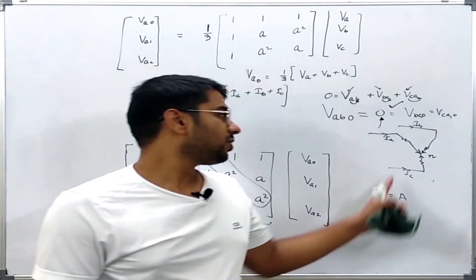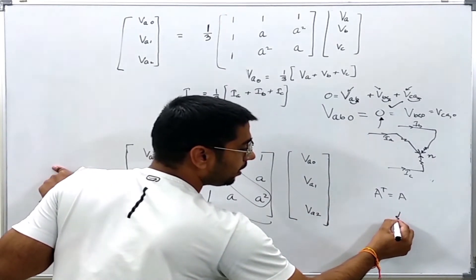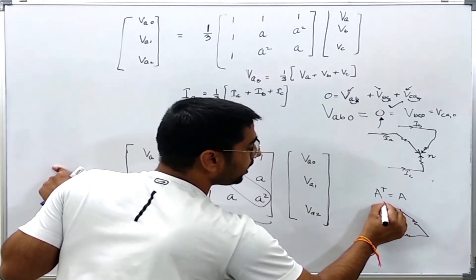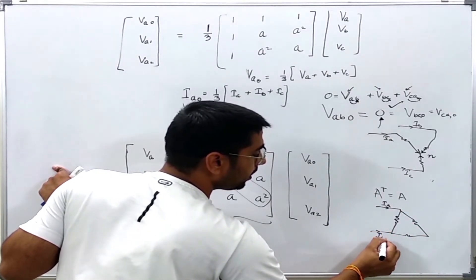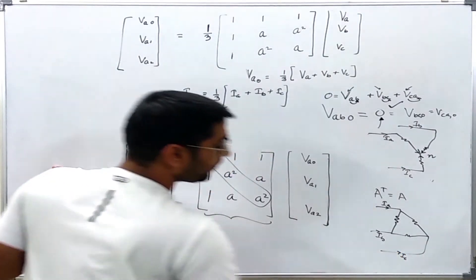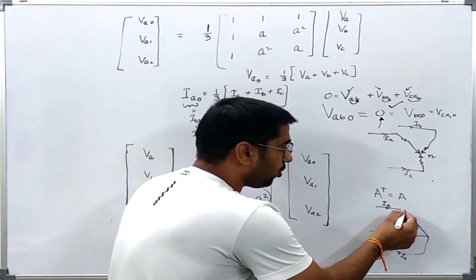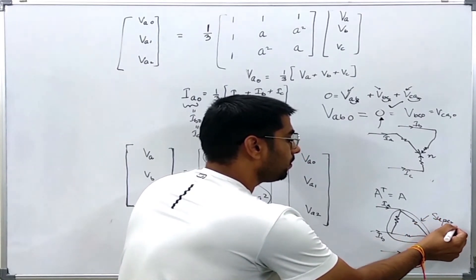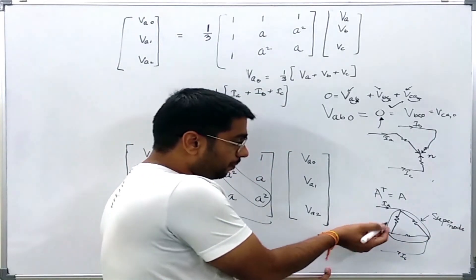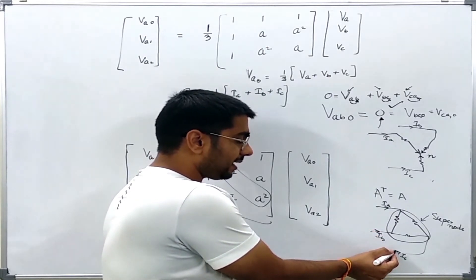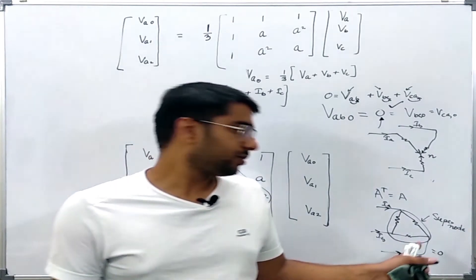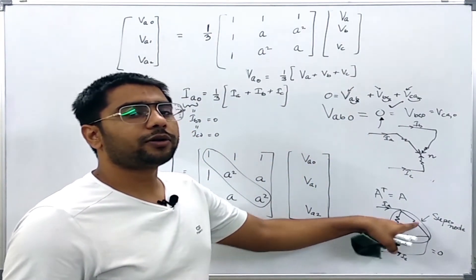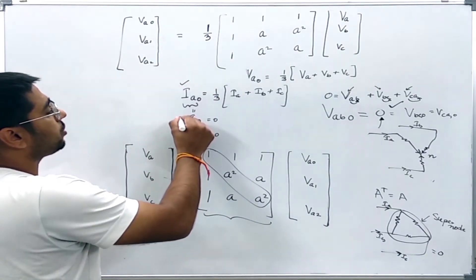For a delta-connected system, we can treat the entire delta load as a super node. From KCL applied to this super node, the sum of all currents entering must equal zero. This clearly shows that a delta connection does not provide a path for neutral currents. Therefore, whenever there is a delta-connected load or delta-connected system, the zero sequence component will always be equal to zero.